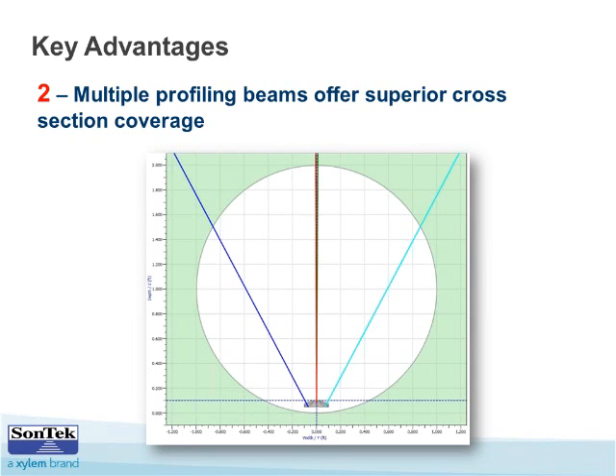We're actually physically measuring it. As Janice pointed out, we're measuring up and down each one of those beams, about every 2.4 centimeters, getting a 2D velocity component. So if you add all 4 beams in, it gives us a 3-dimensional picture of the cross section of the pipe you're measuring.